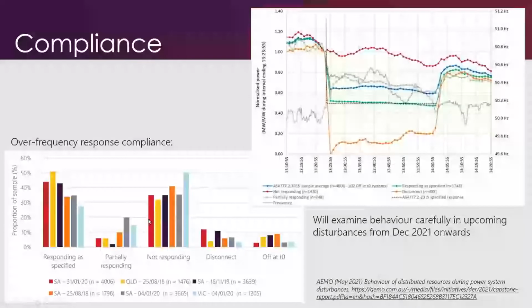These numbers here show you the percentage that fall into that category across a bunch of different disturbances that we've seen where frequency exceeded these levels. Pretty consistently across all these disturbances, we're seeing about 30 to 50% of them responding as they should, according to that green line, dropping down and reliably delivering that overfrequency droop under the 2015 standard. But worryingly, we're seeing a similar amount, another 30 to 50%, that are not responding at all. These ones in the red just merrily went along, ignoring that frequency event entirely. And these are inverters that were installed under the 2015 standard that specifies they should be dropping down. That's quite worrying. That's a very large percentage of inverters that were not responding in these events.